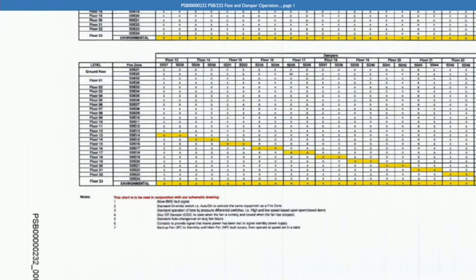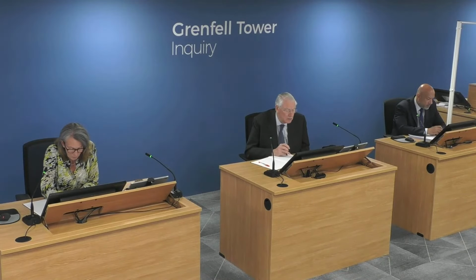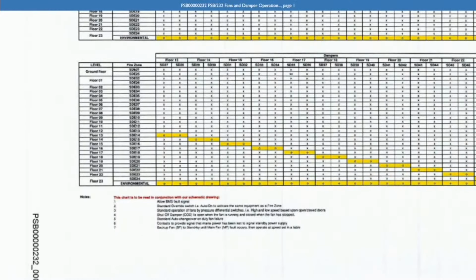Yes, we'll have a look to see if we can see that. I can't see where it says, but obviously I know that once your lobby pressure gets too low, the fans will ramp down. Right. Yeah. Could it be footnote 3? Yeah, it is. Line 3. So it's a standard operation of fans by pressure differential switches, i.e. high and low speed based on open-closed doors.